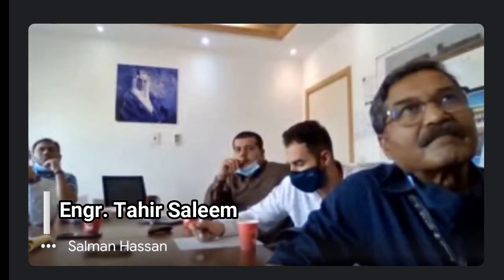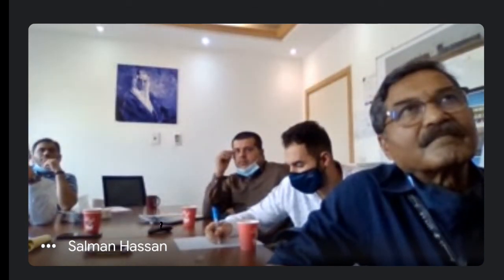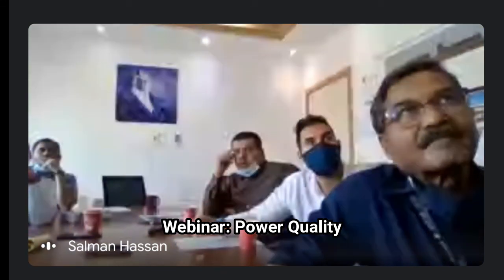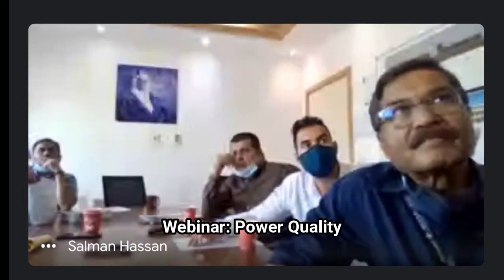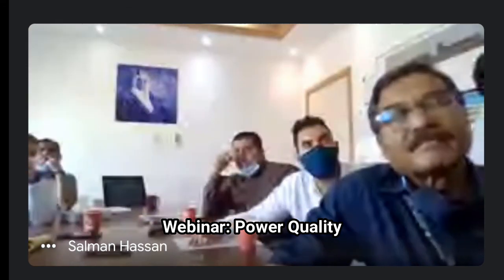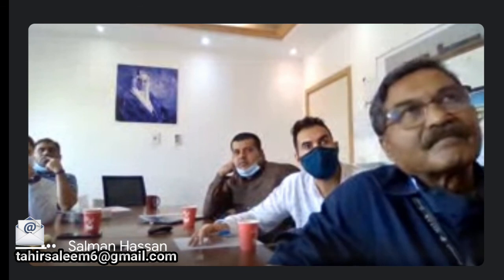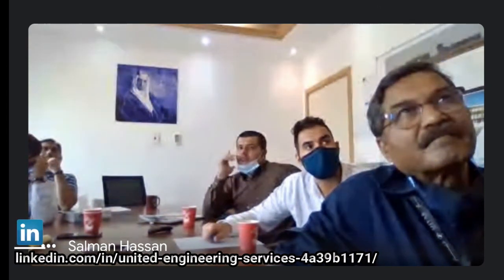In Bangladesh, I have seen it is 0.95. Different countries have their own limitations, because a low power factor means high reactive power consumption and a shortage of reactive power, so that gives a lot of problems. So the utility company, for its own safety, puts in these capacitors. And if those capacitors are placed in a harmonic atmosphere, they will burst because the resonance frequency will destroy the capacitive effect. It is 0.9.